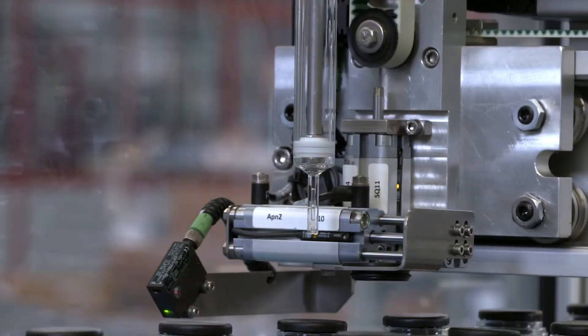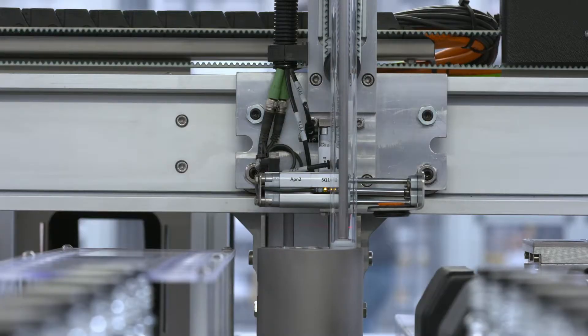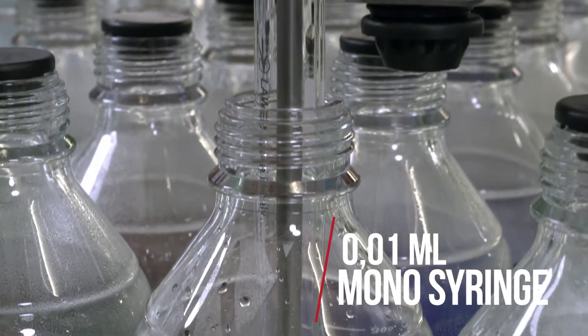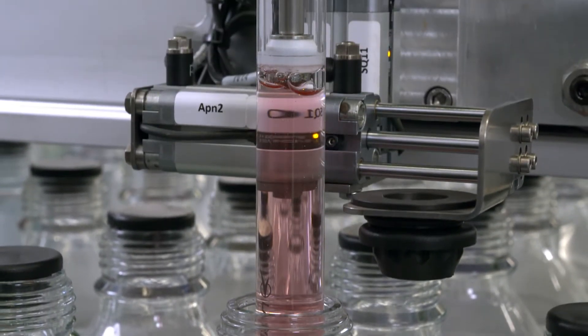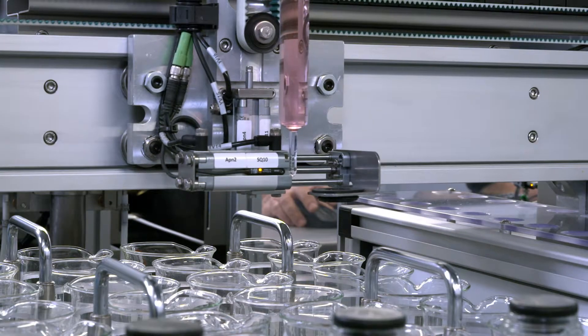The dosing instrument is a Lava patented 55-milliliter syringe with a precision of plus or minus 0.01 of a milliliter, which allows batches to be prepared in the customer's pots or beakers, or put into expellers.